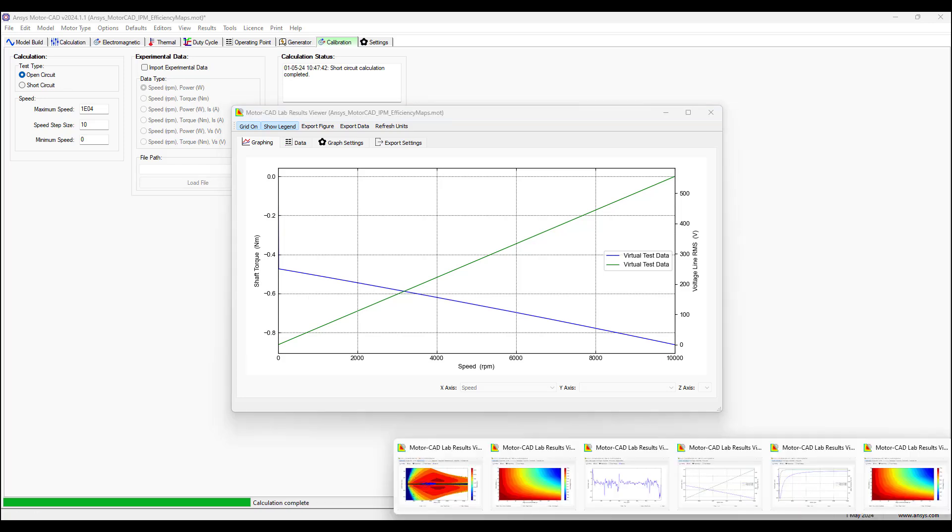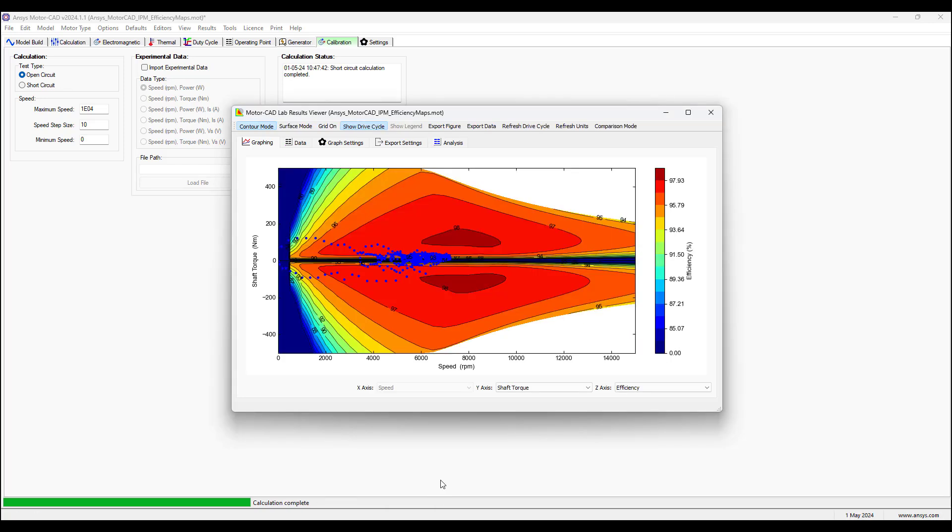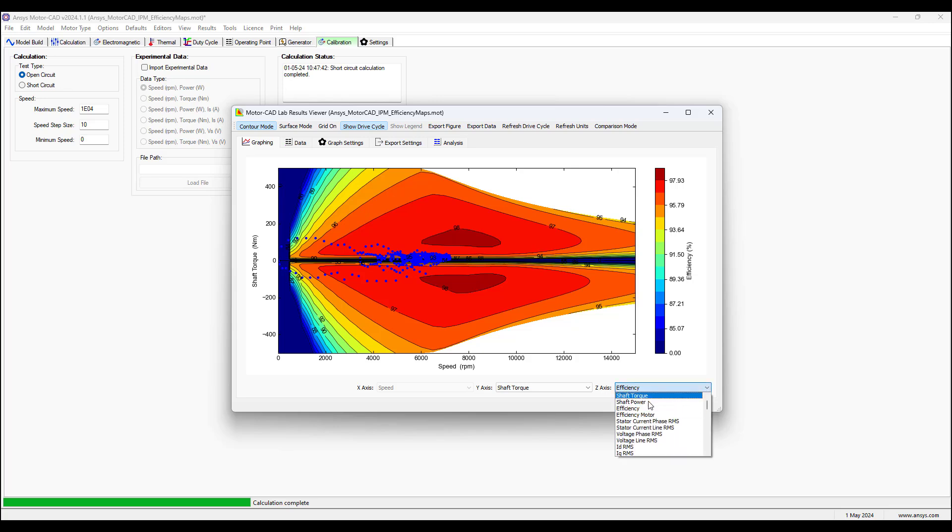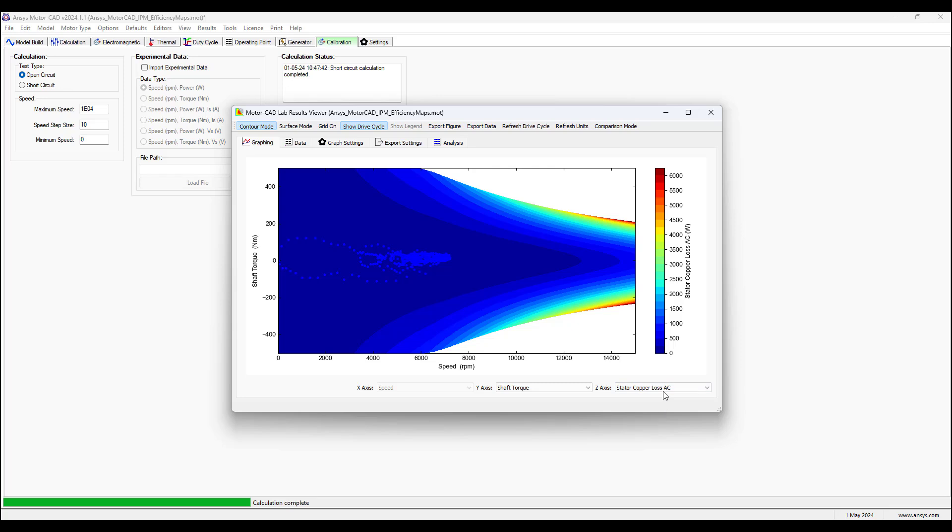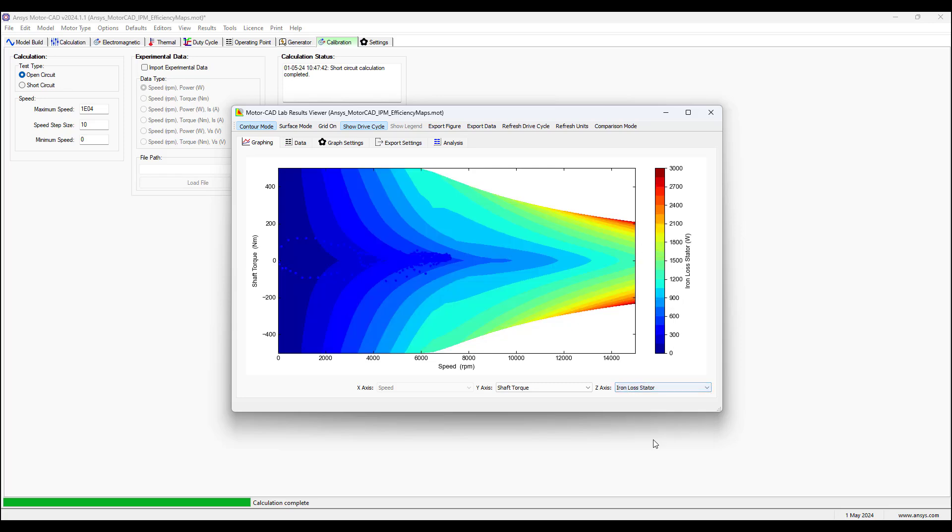Let's go back to the efficiency map shown before. So here in this map, shaft torque along the y-axis and speed along the x-axis are the inputs, and the output is the efficiency shown along the z-axis, which is represented by this color legend. So we see where efficiency is maximum, where it's less, and where it's minimum. By selecting the drop down menu for the z-axis, we can select a different quantity to show along this z-axis, such as the stator copper losses AC. We can see the iron losses of the stator, etc.